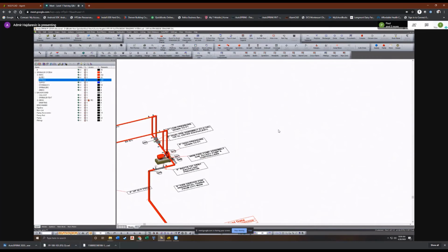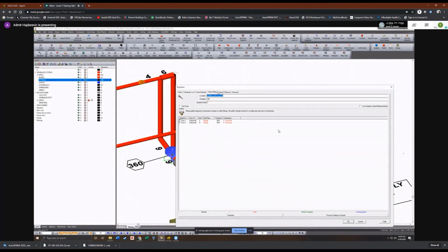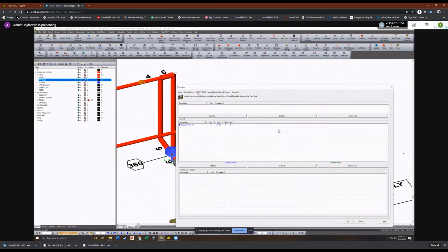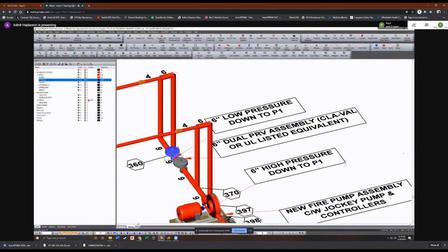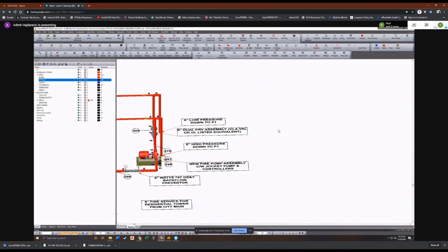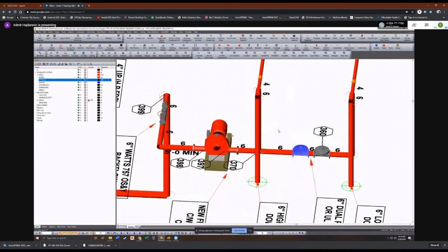No. So the nice thing about a PRV like this for a standpipe system is that you know what your flow rate's going to be. It's going to be 500. So you can establish your pressure loss through this device based on that flow rate and your available inlet pressure at that flow rate. There are going to be a few steps you need to follow here. You need to run the calculation with zero pressure loss through these PRVs to determine your available inlet pressure.